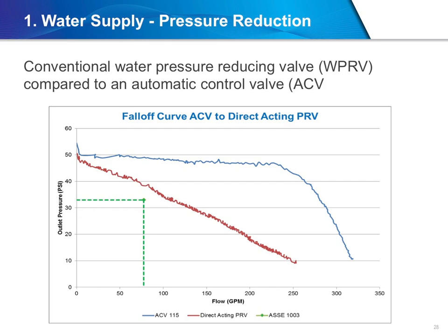The first is a conventional water pressure reducing valve, or WPRV, which reduces fluctuating high inlet pressure to a constant lower outlet pressure. Such WPRVs typically have a broad range of flow potential and can be fully adjustable. For example, a municipal water system that is providing water in the 80 to 100 psi range could be regulated to a constant 50 psi with an appropriately sized and set WPRV. Further, smaller WPRVs could be located within an overall system to be set for different settings to suit the optimal pressure needs of different parts of a healthcare facility.